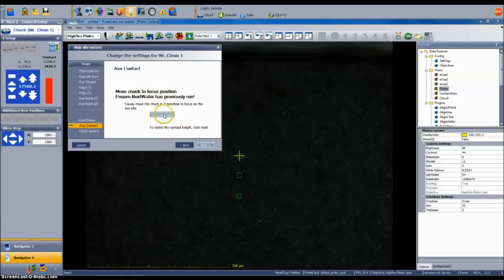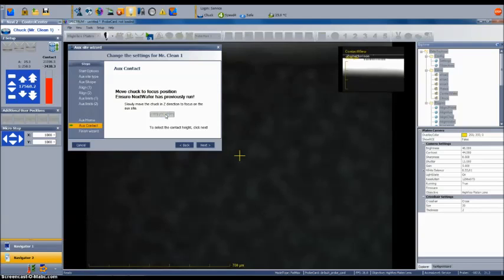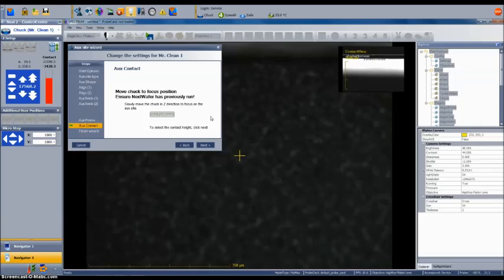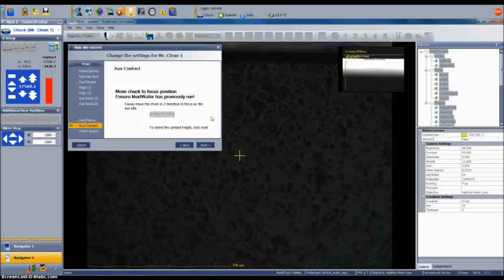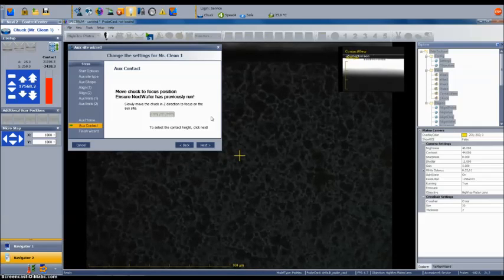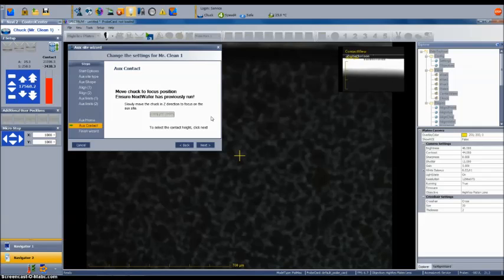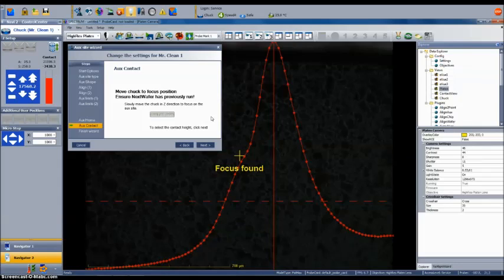Then finally, select the run find focus button to lock in the focus height at the home position. The height of the aux chuck will be used in conjunction with the probe tip height and the wafer surface height that were found during the next wafer operation.